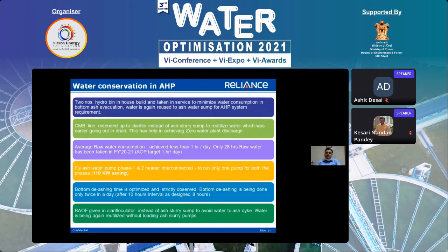It is a model equipment for us. In that hydro bin, the water is segregated from the bottom ash, and the ash is collected. That ash is a coarse ash, so we are filling it into the bulkers, and it is being used in land filling. The water we are using again in our clarifier in the AHP, so that our whole wet ash system will be catered by the water system only. So that coarse ash is also being utilized, and our new initiative of making the hydro bin is 100% successful here. The CMB line is going to the clarifier instead of the ash slurry sump.